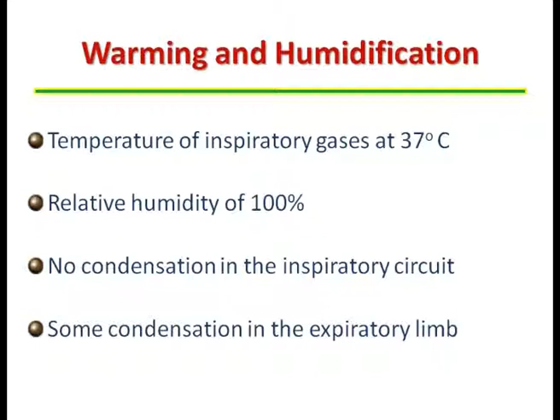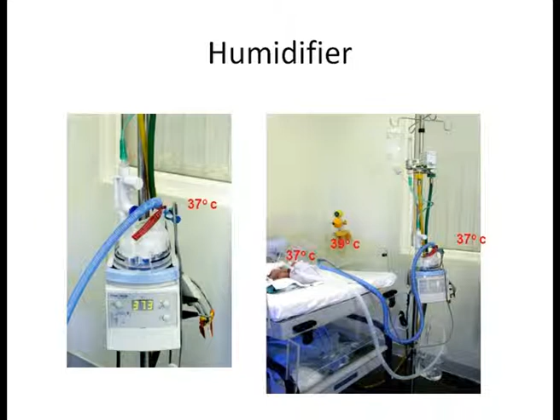Here we can see the gas temperature coming from the humidifier is at 37 degrees Celsius and it is getting warmed in the inspiratory limb with a heater wire. The blue circuit with a heater wire is the inspiratory limb. The gases are warmed from 37 to 39 degrees and beyond that blue limb, the gas is getting cooled to 37 degrees before it reaches the nares. You will not be seeing any condensation in the blue circuit part of the respiratory circuit. However, in the expiratory limb, the gas temperature would come down to room temperature and then one could see condensation in the expiratory limb. This excess water trickles into the bubble chamber.